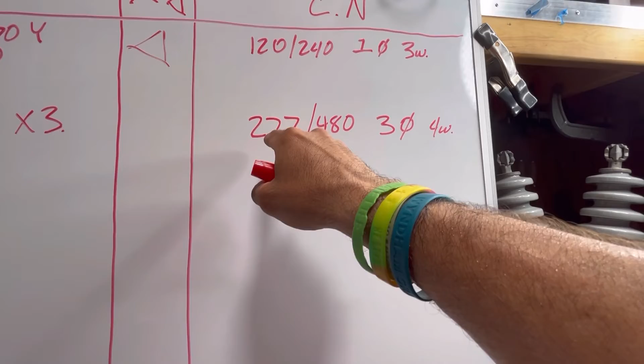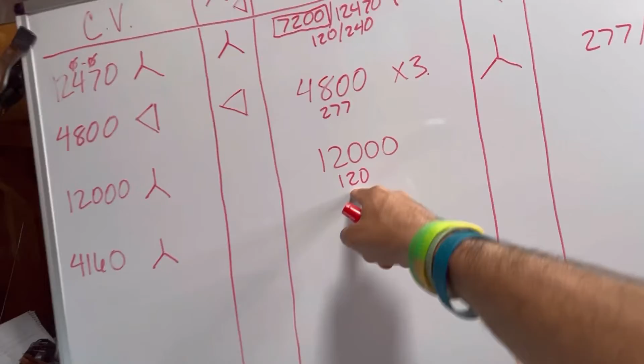Next one, we've got 12,000 Y. Let's say my transformer nameplate just says 12,000, 120 output. So 120 volt output. My customer needs, let's say, 120/208, 3-phase, 4-wire. So moving over here, starting in my primary, does this number match that number? If the answer is yes, we know that it's going to be a delta hookup.